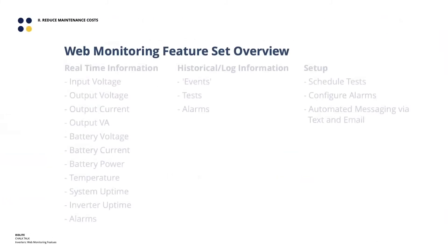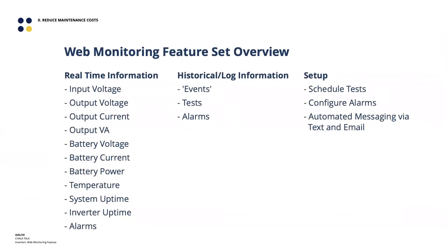The feature set of the web monitoring portal is pretty comprehensive — it covers basically everything the inverter is capable of reporting. From a real-time perspective, that includes input and output voltage, input and output current, the actual connected load attached to the device, battery health information, system temperature, uptime — how many hours the inverter has been active — and any current alarms like a tripped circuit breaker. Anything that can be reported in real time can also be reported up to this web portal.